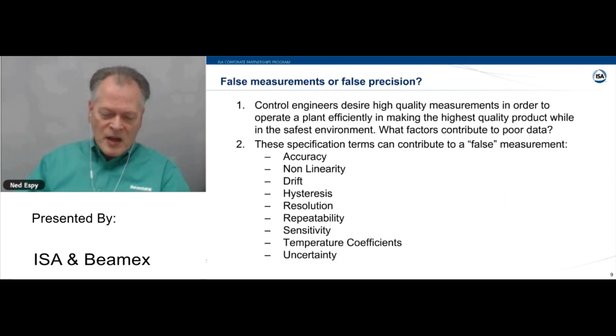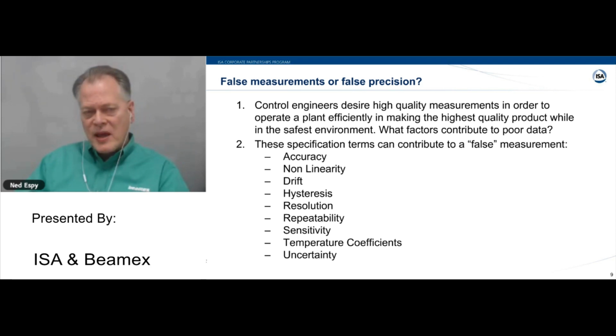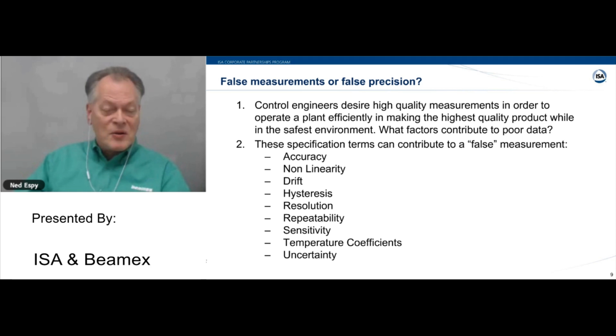So on the flip side, when you look at a process plant, the control engineer who's designing the plant to produce high quality product in a safe environment wants good data. If you're a technician and your calibration of an instrument for whatever reason is off, basically you're providing poor data, or really bad data, to the control engineer, and they cannot make good decisions with poor data. They need the best data that you can deliver.